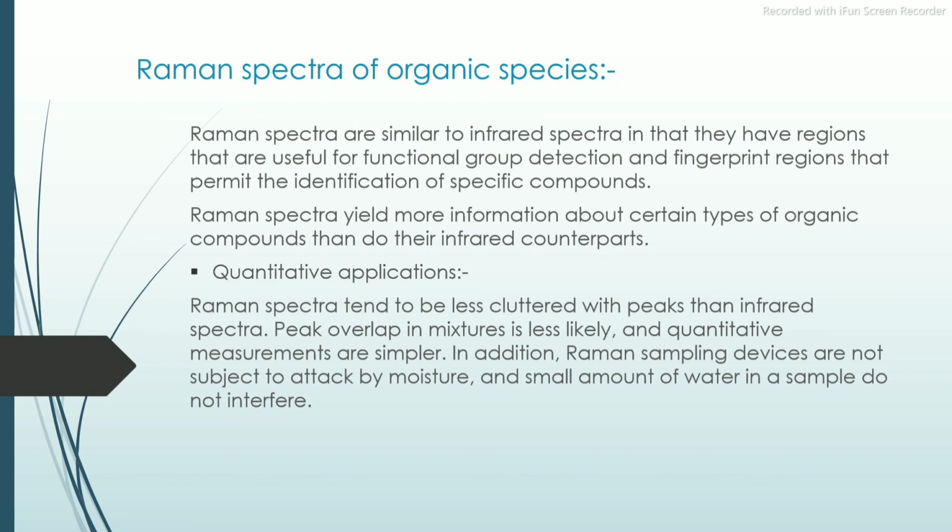Then quantitative application. Raman spectra tend to be less cluttered with peaks than infrared spectra. Peak overlap in mixtures is less likely and quantitative measurements are simpler. In addition, Raman sampling devices are not subject to attack by moisture and small amounts of water in a sample do not interfere.